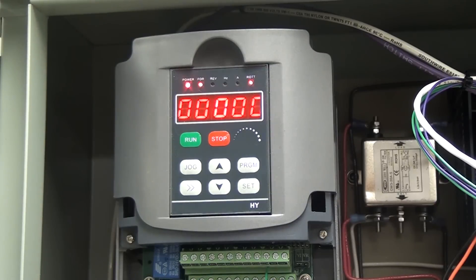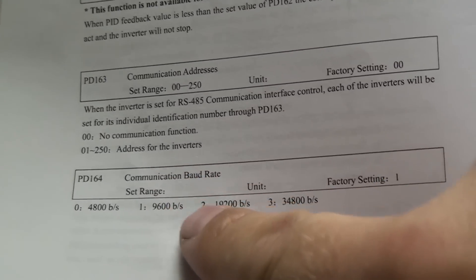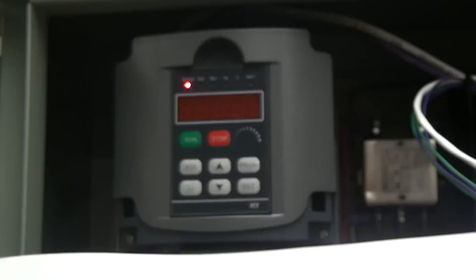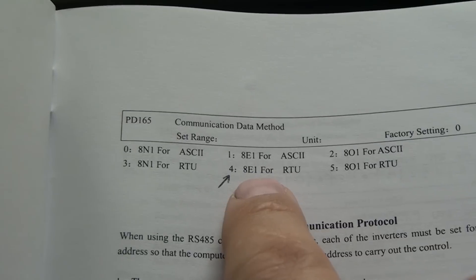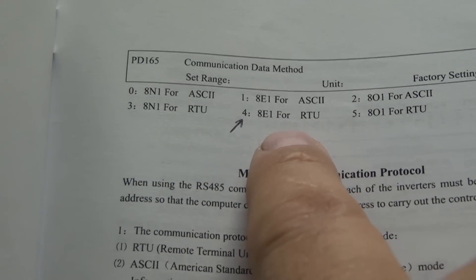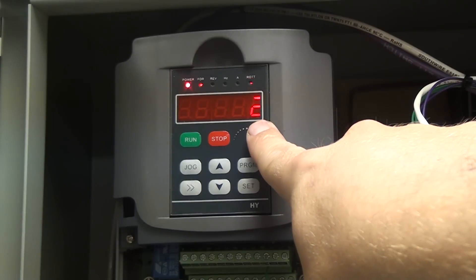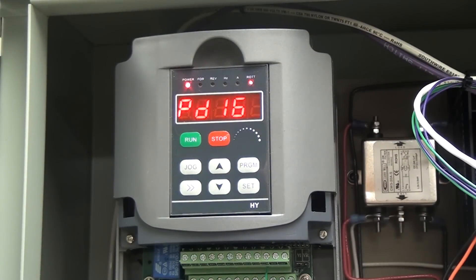The last thing I want to talk about is program 164 — communication baud rate — which should be set at 19,200 bits per second. I'll show you: 164 will be a 2, and 165 will be a 4. That is for Communication Data Method 8E1 for RTU. I have no clue what this means — just make sure yours is set up this way. Sure enough, there's a 2 for 19,200 bits per second, and 165 is a 4 for 8E1 RTU communication data method. Hit set and just double check those — I think that's the default setting, but double check them anyway.